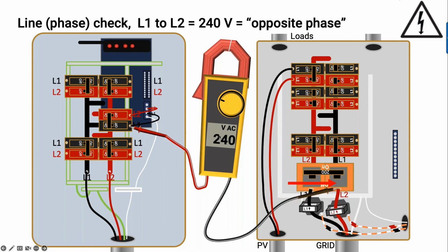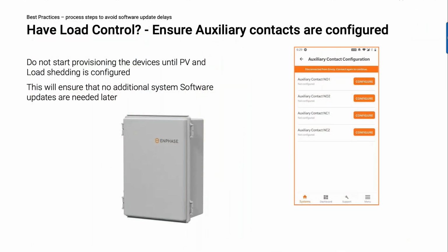If you see 240 volts, and if your meter lead is on line 1 and you go over here and that's on line 1 and it reads 240 volts, you've got a crossed wire. It's wired through incorrectly, or you may have one of those circuit breakers that has cross phases when power goes through the circuit breaker. All right, I spent a little bit of time on this, but I think it's important because CTs, again, have errors.